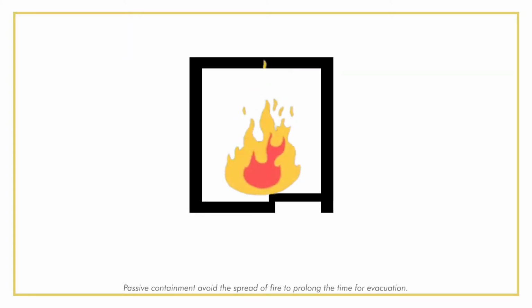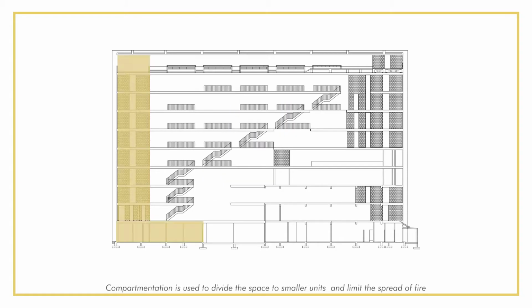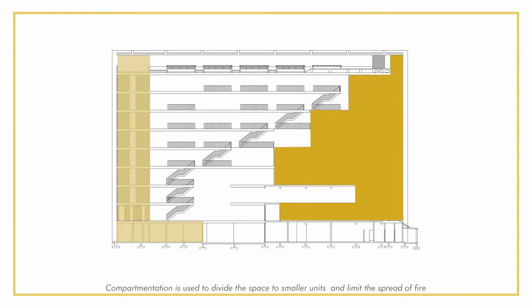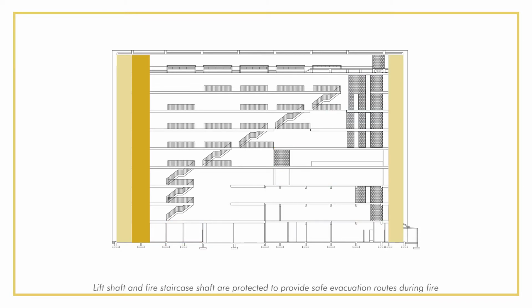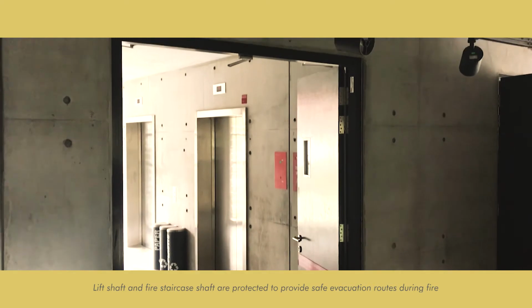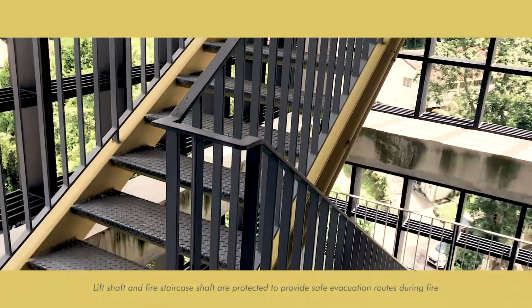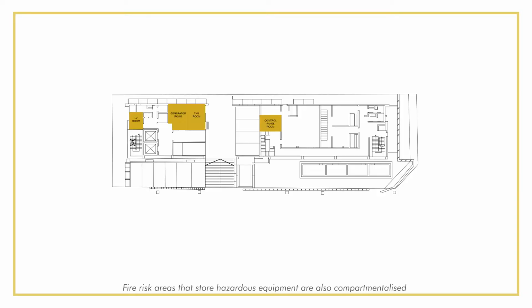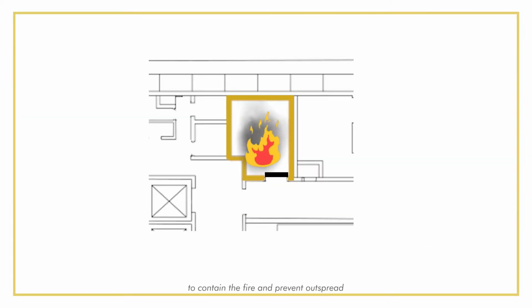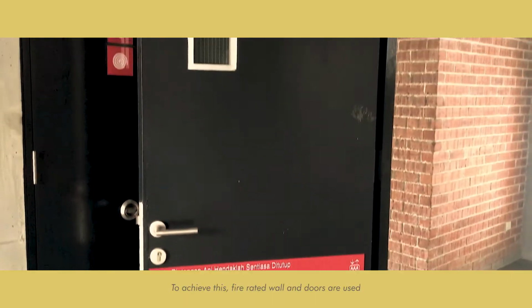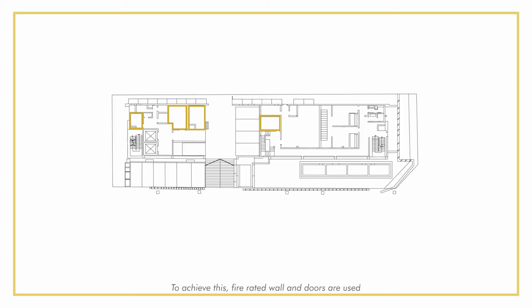Passive containment avoids the spread of fire to prolong the time for evacuation. Compartmentation is used to divide the space into smaller units and limit the spread of fire. Lift shaft and fire staircase shaft are protected to provide safe evacuation routes during fire. Fire risk areas that store hazardous equipment are also compartmentalized to contain the fire and prevent outspread. To achieve this, fire-rated walls and doors are used.